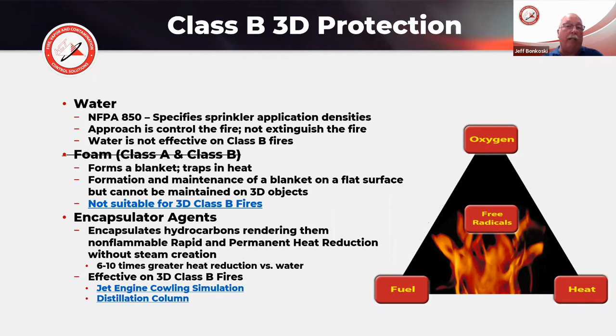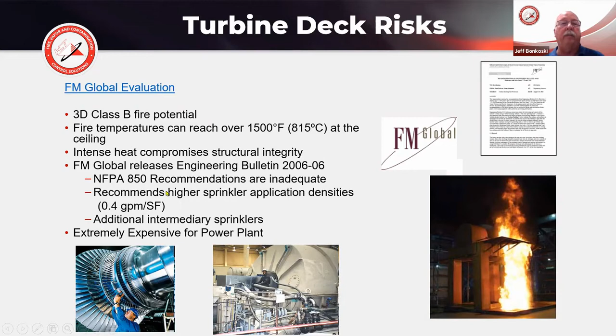Under turbine lube oil protection. Again, with some of the fires and some of the testing with FM Global, we're talking about reaching temperatures in excess of 1500 degrees at the ceiling. Because of these high temperatures, they're saying we need to increase our sprinkler densities. The densities currently in place aren't adequate, so they started putting out bulletins and making recommendations for a higher flow. And when you look at some of these older facilities, we could be looking at millions and millions of dollars to replace water mains and all the piping. It can get rather expensive.